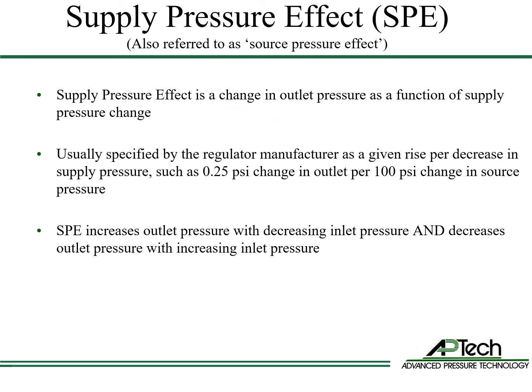Supply pressure effect is a change in outlet pressure as a function of supply pressure change. This effect is usually specified as the change in outlet pressure per change in inlet pressure — for example, 0.25 psi change in outlet pressure per 100 psi change in inlet pressure. Normally, supply pressure effect is encountered when the inlet pressure decreases as gas cylinders are consumed. As a result, outlet pressure increases as a gas cylinder is consumed. However, the supply pressure effect works with both decreasing and increasing inlet pressure: an increase in inlet pressure will cause a decrease in outlet pressure at the same rate as specified.